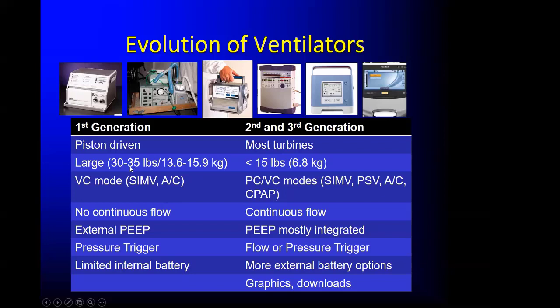These guys were considered portable, but they were beasts. So a 35-pound ventilator, and if you wanted to make it truly portable, you had to add a marine battery. So think about the weight of that plus lugging the toddler around attached to it. Now these machines are quite small and quite nimble, and most have internal batteries. The initial machines only delivered breath in a volume control mode, and there were only two schemes. That was synchronized IMV and assist control.